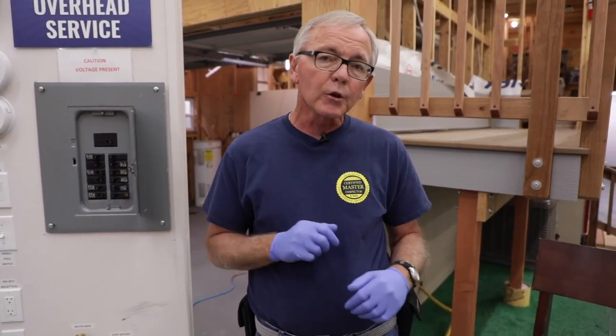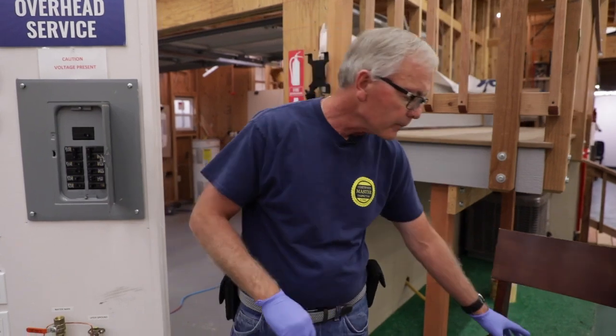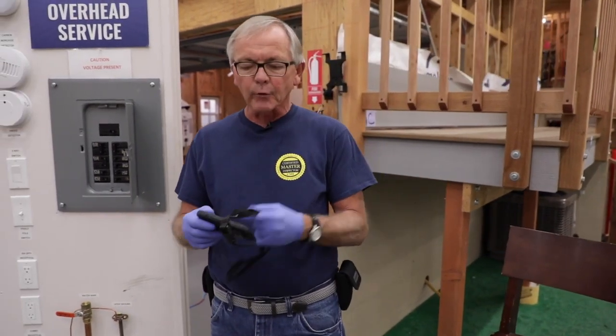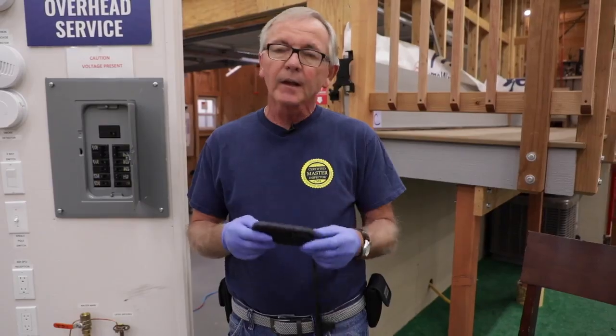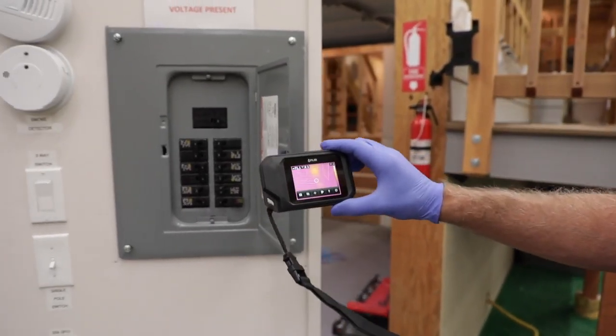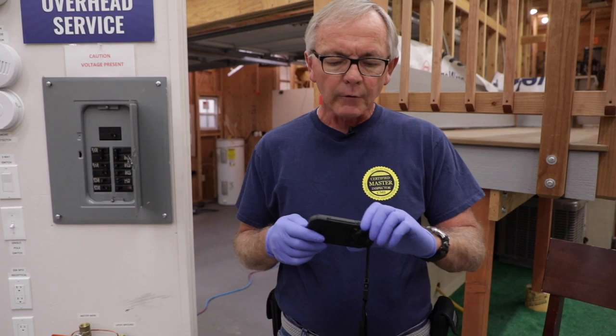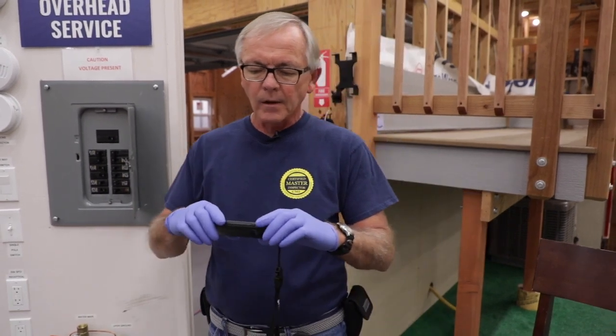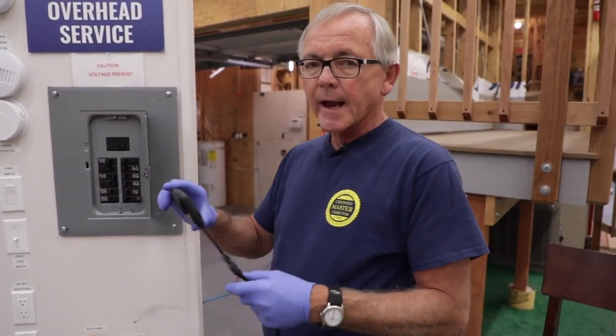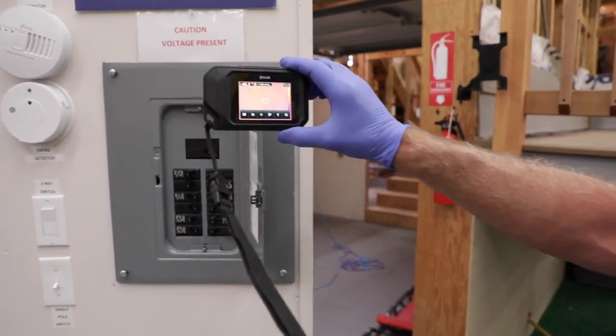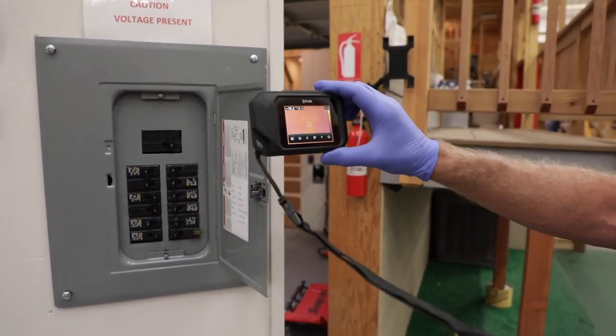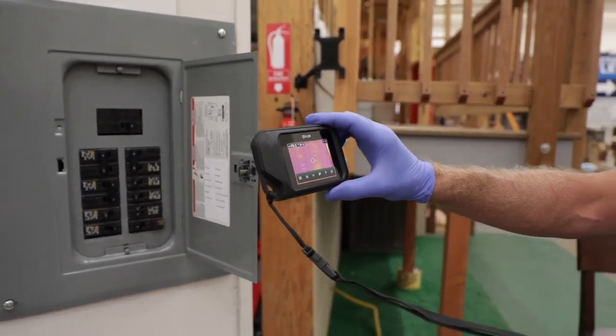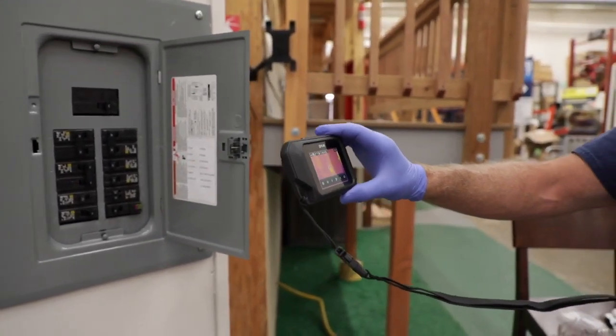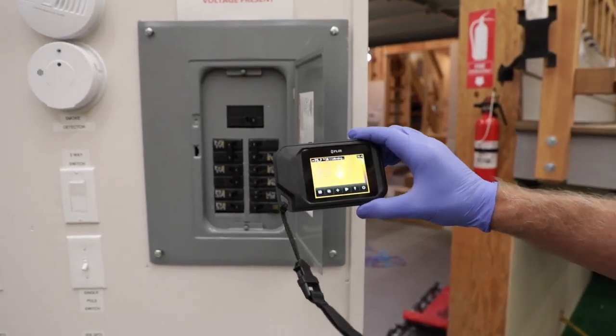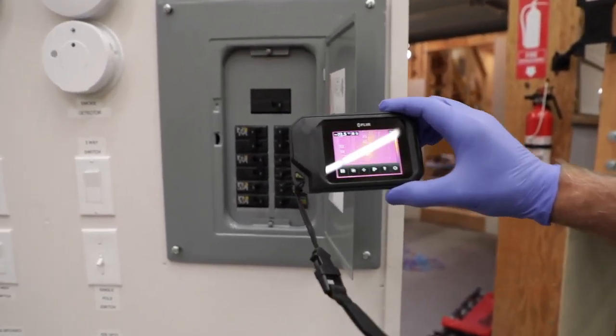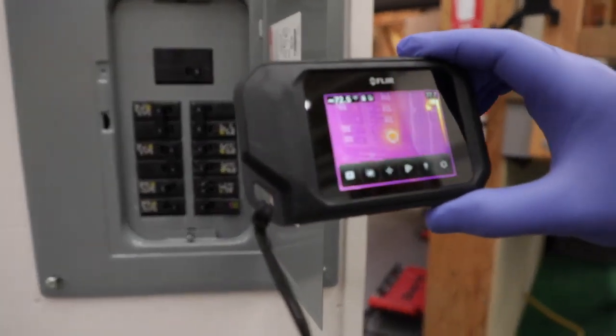But one other thing I'm going to do first, if you're using infrared with your inspections, this is a great tool to use for the inspection of the electrical panel. The first thing I do is turn it on, and now I'm going to do a quick scan with the cover on the panel. I'm just going to go down from the top to the bottom to see if I have any hot breakers or overloads. You might see this one bright yellow spot down at the bottom right there. That's an arc fault breaker.